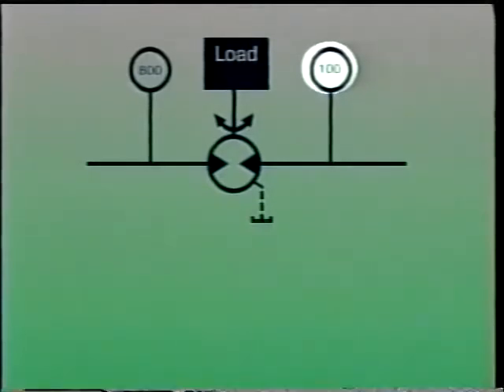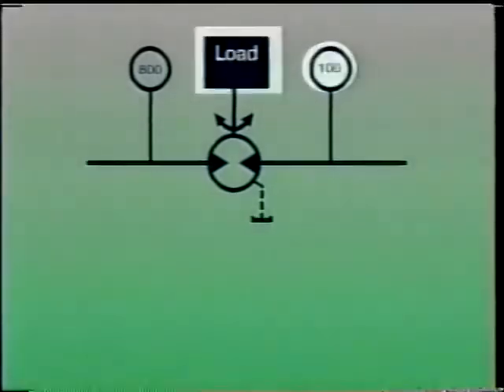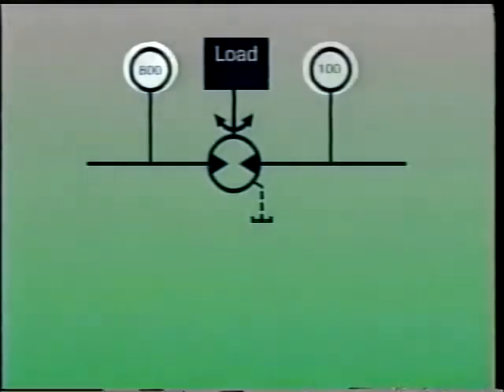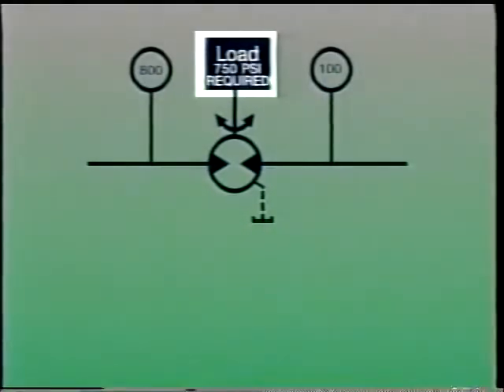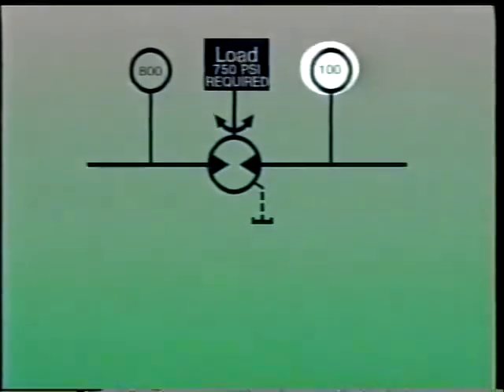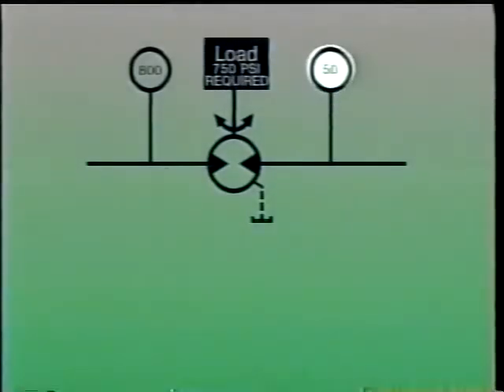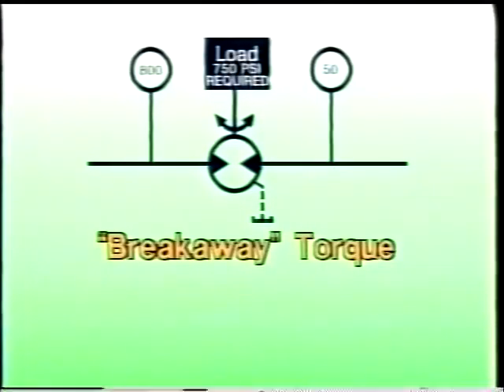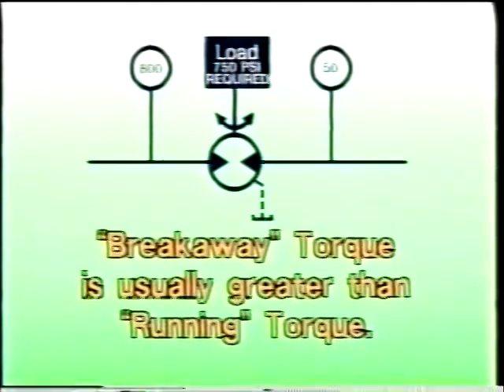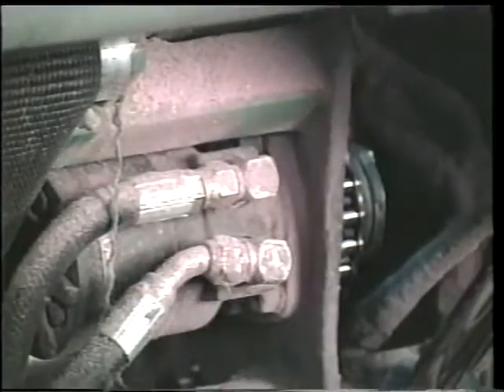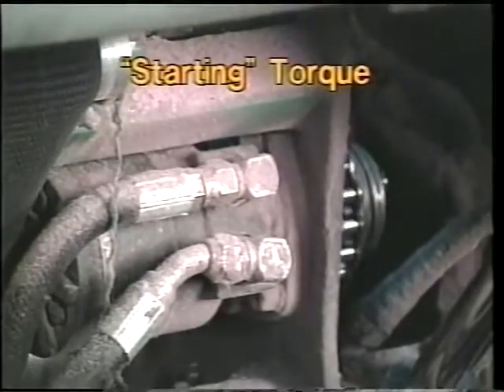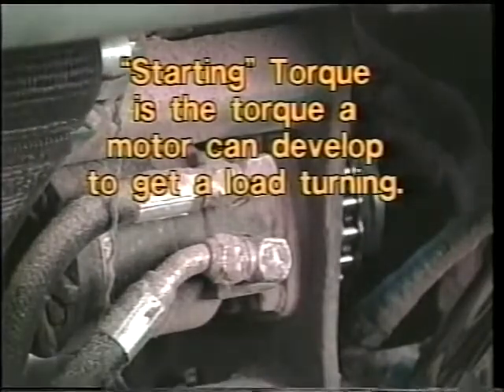In this system, 100 psi back pressure prevents the motor from moving the load because back pressure attempts to turn the motor in the opposite direction. 800 psi less 100 psi back pressure leaves only 700 psi available for a load which requires 750 psi to move. Even 50 psi of back pressure could prevent the load from turning, because the breakaway torque — the torque required to get a load turning — is usually greater than the running torque required to keep a load turning. Industrial motors are rated for breakaway torque, running torque, and a third kind: starting torque, which is the amount of torque the motor can actually develop to get a load turning.